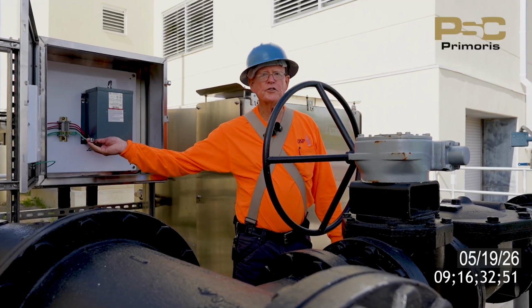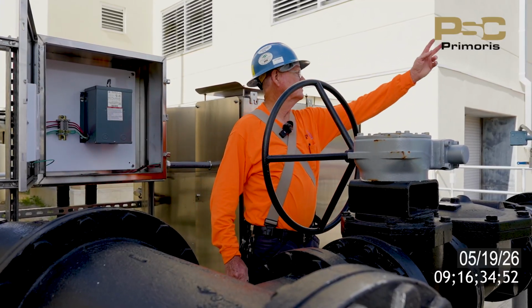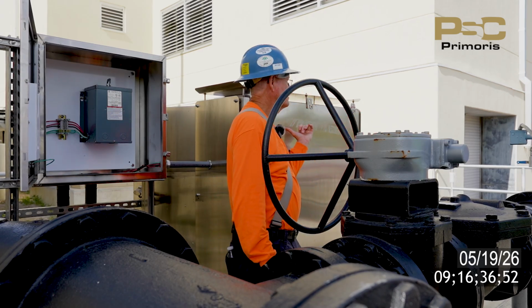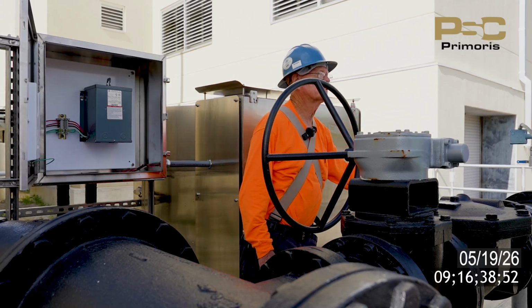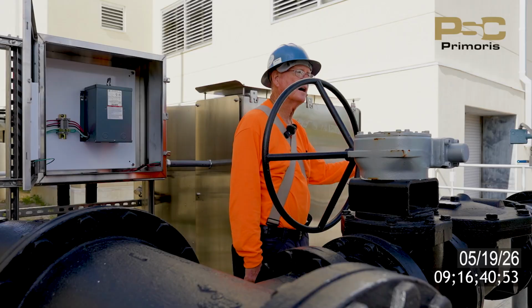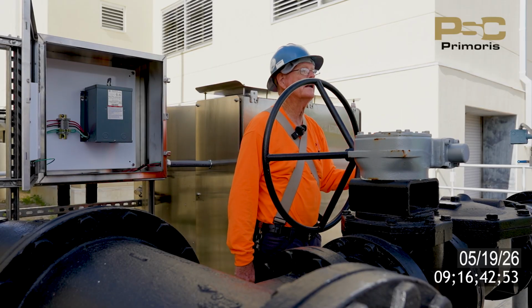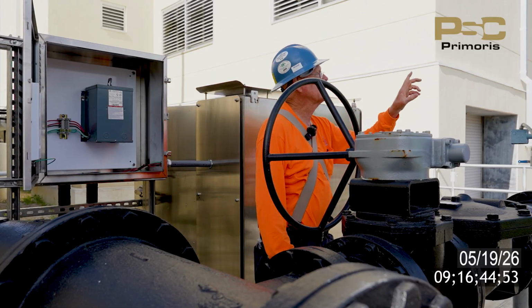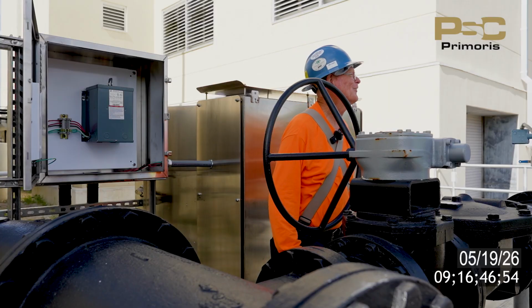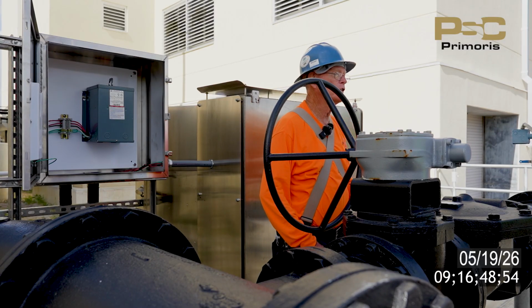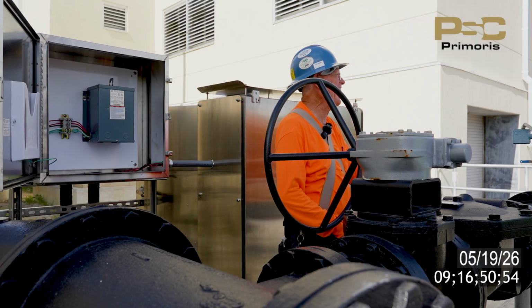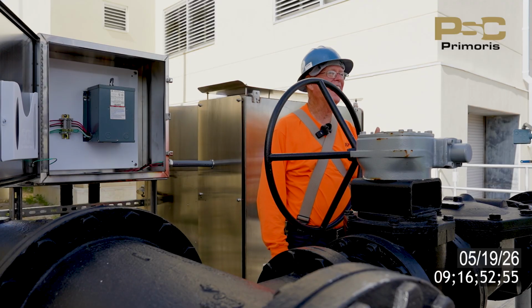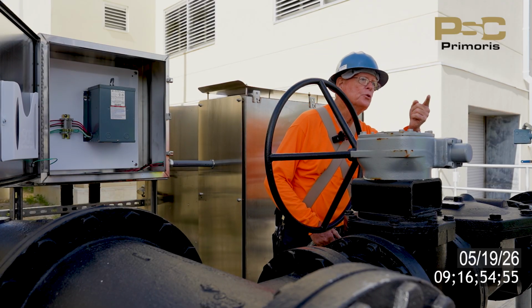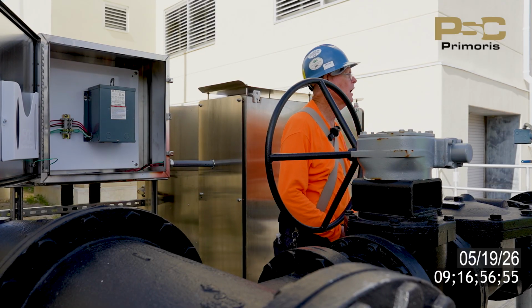So, transformer, junction boxes, level transmitter, control panel, pumps, pressure switch — that's it. And anytime you need to run it in hand, if you turn it to hand, it's going to stay running. The low level float will not shut it off. So you can run this thing until it goes, because if you turn it to hand, you told it to run, it's going to run.